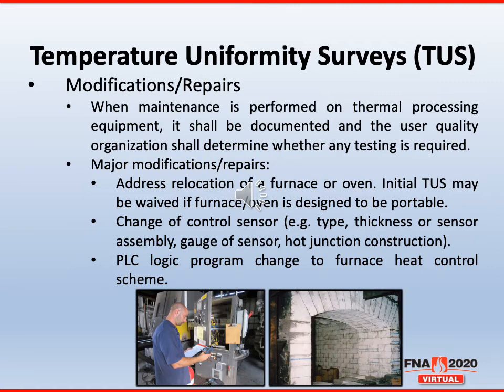We also require an initial survey if the control sensor is changed. That means if the type or the thickness of the sensor, or the sensor assembly, the gauge of the sensor, or the hot junction construction has changed, that could actually have a major effect on thermal processing equipment. If you also change the location, which was also in the previous revision, that required an initial survey. But now we're saying if the construction of the thermocouple that you may be changing is different, again, if it's a different size, diameter, or the hot junction is exposed versus unexposed, then an initial survey will be required. If there's also a change in the PLC logic program for a furnace that changes the heat control scheme, an initial survey will be required as well.